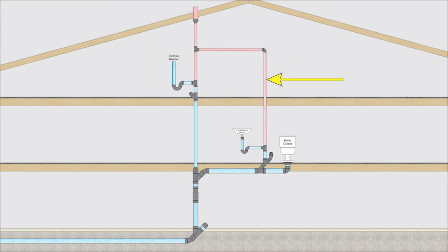Now this little vent pipe coming off the powder room from the main floor is going to have no effect on this whatsoever. That's a minor vent called a continuous vent. We'll be covering that in a future video. But it doesn't change anything to do with the stack vent because everything from that powder room is already draining through the stack, therefore it's being counted in the stack vent.